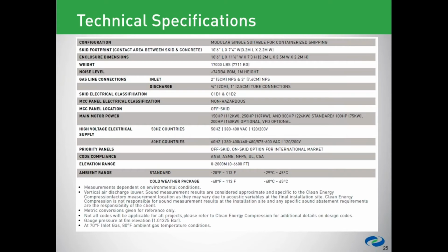Here's an interesting one. If you have 2 compressors connected together with only one running, is there a barrier between them to prevent warm air from recirculating? Yes, there is. So we actually remove the aluminum skin off the exterior of the package, but the interior wall panel remains, and so there you still have the insulation and perforated carbon steel skins between the two packages, and that does 2 things.